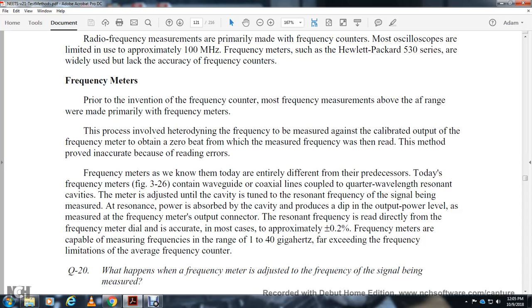Today frequency meters contain waveguide or coaxial lines coupled with a resonant cavity, the wavelength of which is adjusted by the meter to assume the resonant frequency of the signal being measured. The resonant power absorbed by the cavity produces a dip in the output power level. The frequencies are read directly from the frequency meter dial with an accuracy of approximately plus or minus 2 tenths of a percent. Frequency meters are capable of measuring frequencies from 1 to 100 gigahertz, exceeding the frequency limitation of average frequency counters.